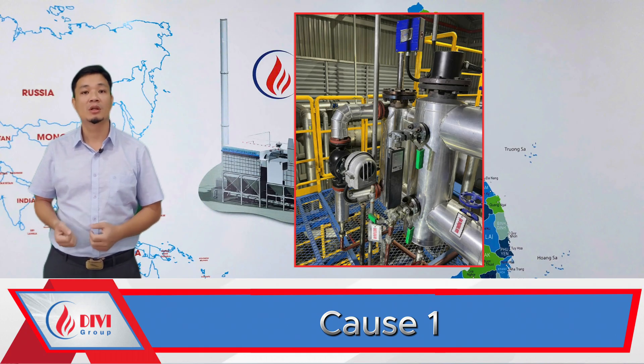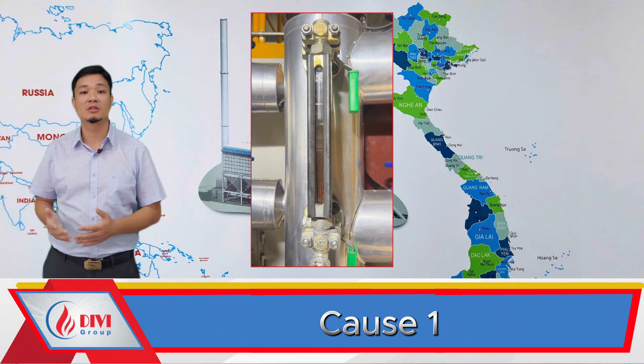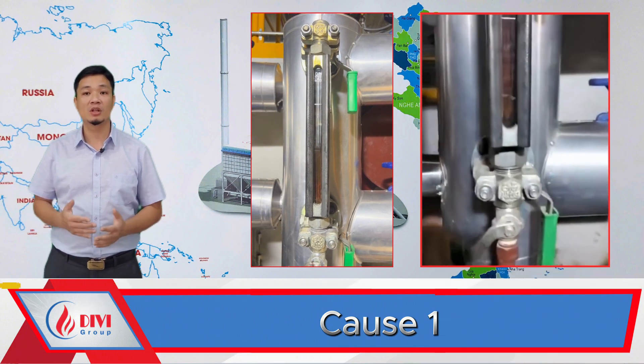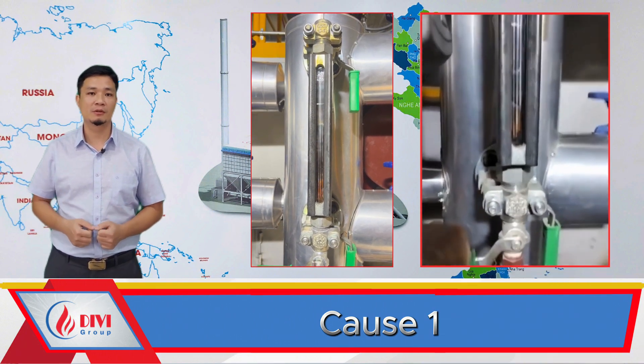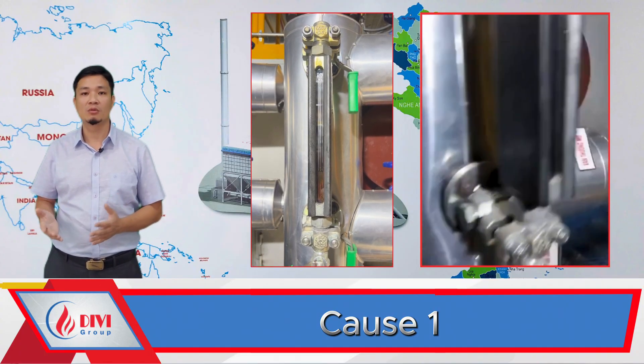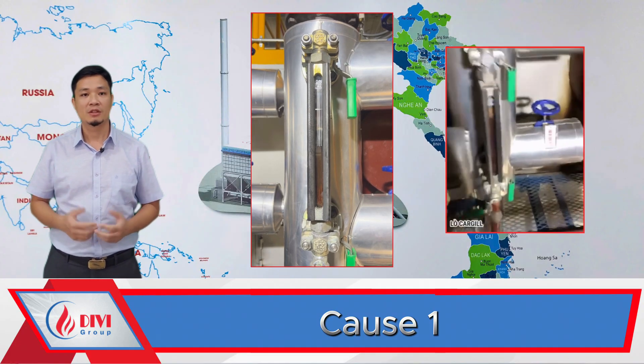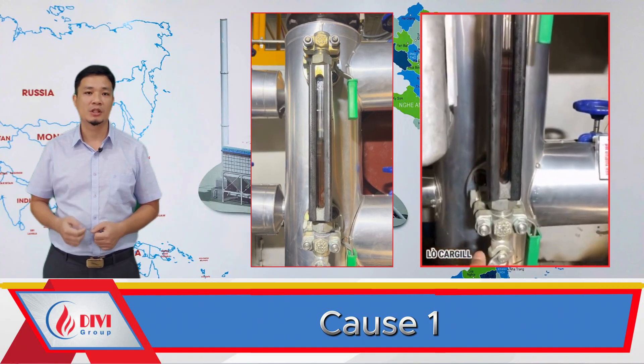Meanwhile, combustion and oxygen supply remain the same, so steam generation drops. To verify this, check the water level gauges. If both show equal levels within the safe range, this isn't the issue. If no level is visible, the drum is likely overfilled. To confirm, blow down the sight glasses. If readings are inaccurate, inspect and replace the level sensors immediately.